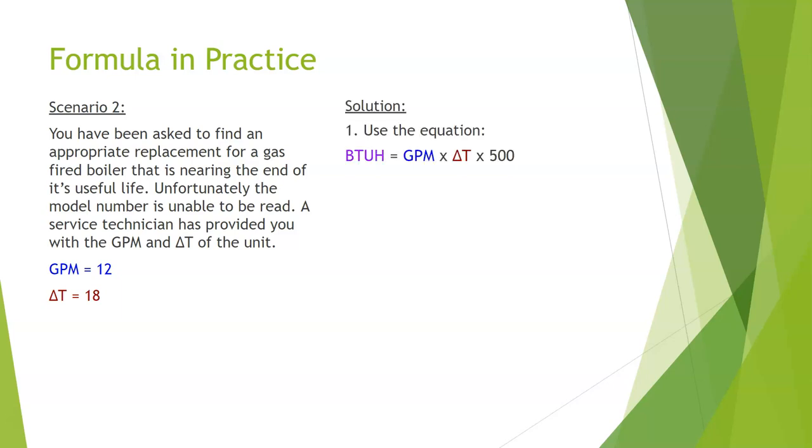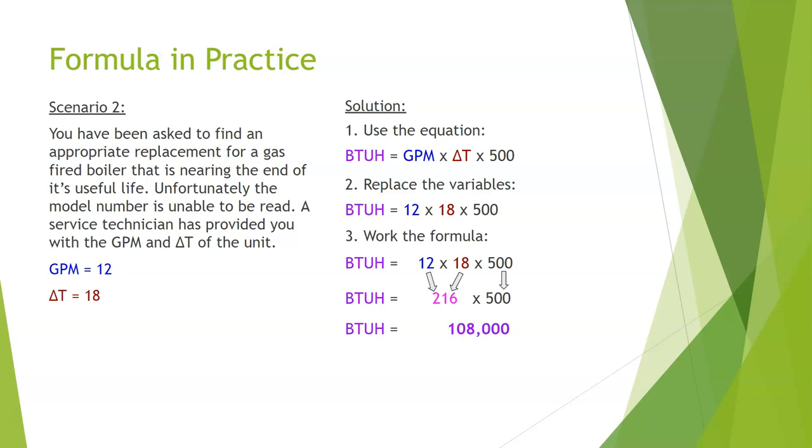Let's work the solution. First, I'm going to write down my equation: BTU equals GPM times delta T times 500. Then I replace my variables. My GPM is 12, my delta T is 18, and my magic number is still 500. I work the formula: BTU equals 12 times 18, which gives me 216, times 500. That gives me 108,000 BTUs.